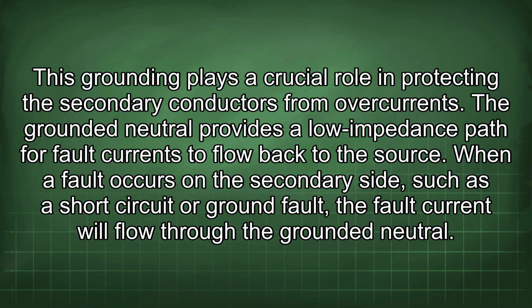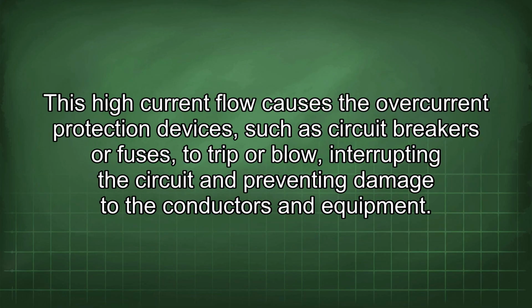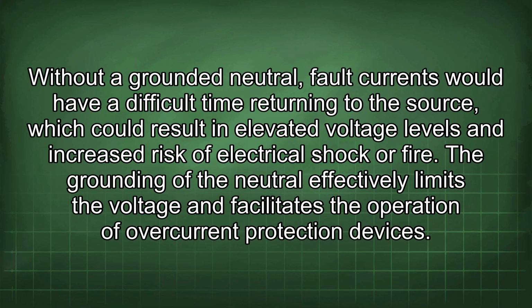When a fault occurs on the secondary side, such as a short circuit or ground fault, the fault current will flow through the grounded neutral. This high current flow causes the overcurrent protection devices, such as circuit breakers or fuses, to trip or blow, interrupting the circuit and preventing damage to the conductors and equipment. Without a grounded neutral, fault currents would have a difficult time returning to the source, which could result in elevated voltage levels and increased risk of electrical shock or fire. The grounding of the neutral effectively limits the voltage and facilitates the operation of overcurrent protection devices.